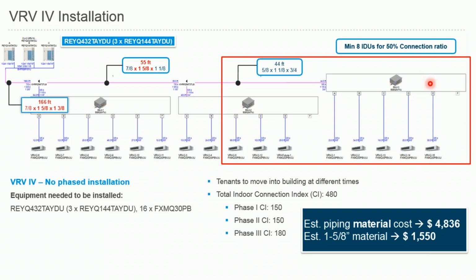And to get the minimum connection ratio, you had to install 8 indoor units, even though you only need 150 connection capacity index for your first phase, which is over here. Instead of just installing 5 indoor units, FXMQ30, to get to your minimum connection ratio, you had to install this additional branch selector box and 3 more indoor units. And that's how you started your initial stage of the project with VRV4. And once more tenants start moving in, you will need to add more indoor units and whatnot as well.